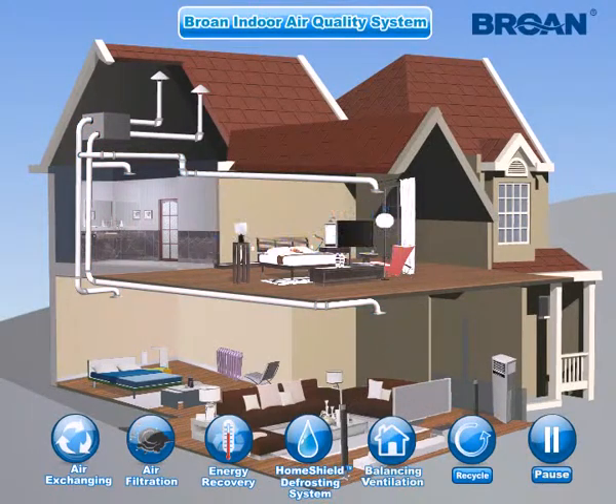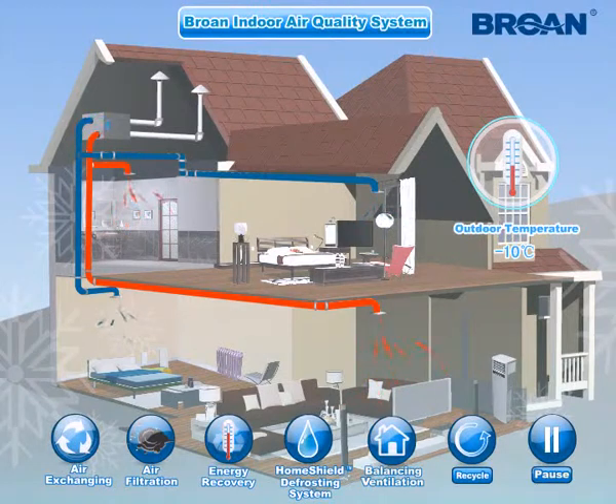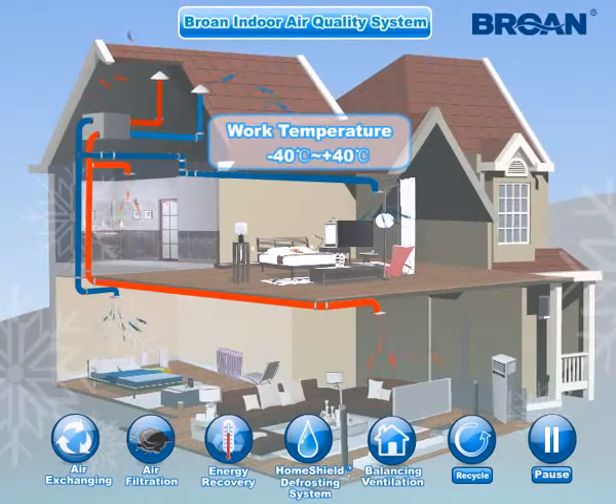Home Shield Defrosting System: The Broan IAQ system automatically starts recirculation mode when outdoor temperature is extremely low. In this mode, indoor temperature is utilized to prevent ice build-up on the recovery module without creating negative indoor air pressure. The system keeps indoor air recirculation and filtering, but stops exchanging air with outside. The Broan IAQ system can work normally at temperatures from minus 40°C to plus 40°C, making it suitable for almost any climate.